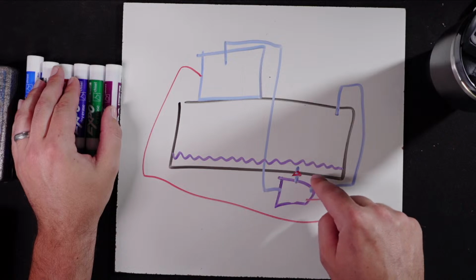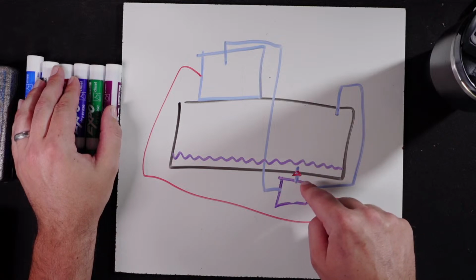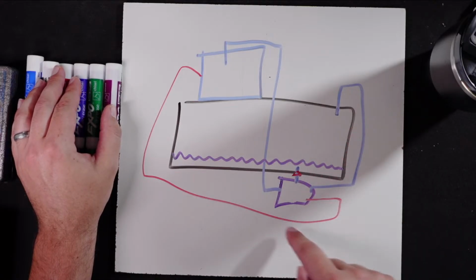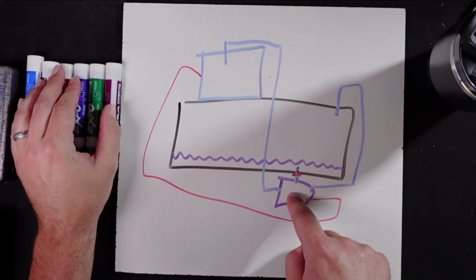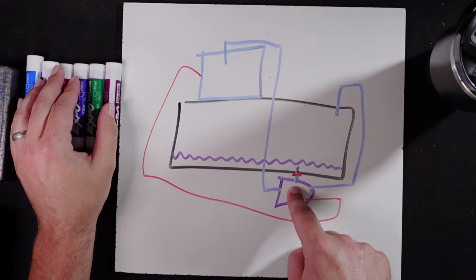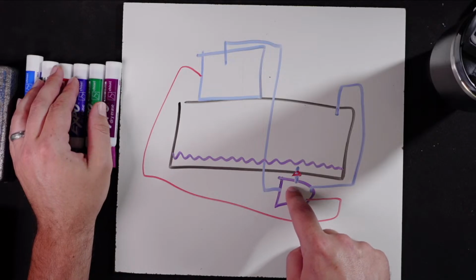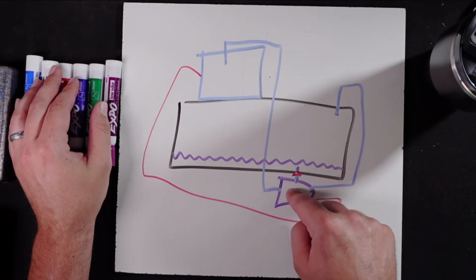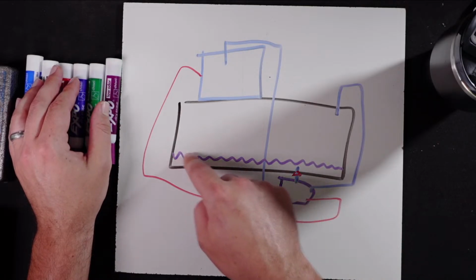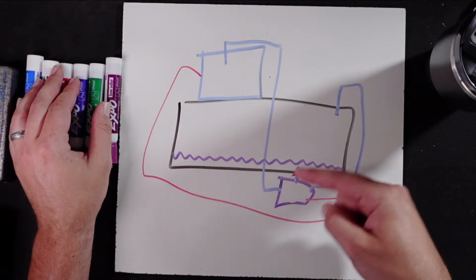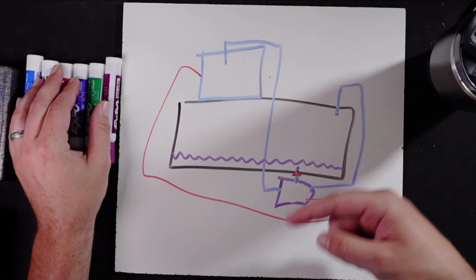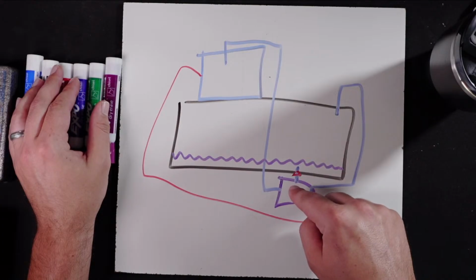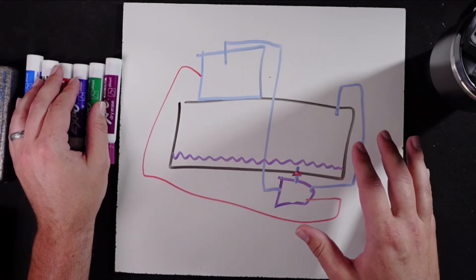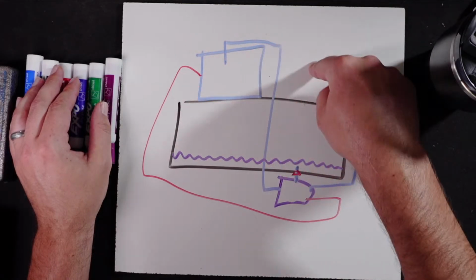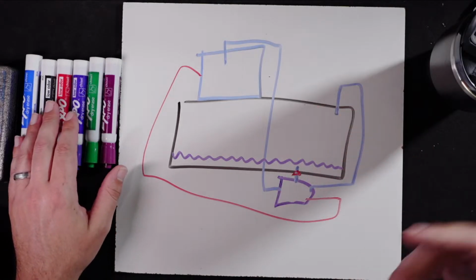And if this can't happen fast enough, or it's not going to happen that fast, is what I'm trying to say. Because we've got to fill this chamber, and this is on a time cycle, and I'd have to look at the books, but it's several minutes per cycle. Minutes per cycle. That is just one. And you got to think, a small volume of oil is actually getting captured into this chamber compared to what is stacking in the evaporator. And we need to get several cycles through, like a lot of cycles have to process through this pump in order to get the oil charge that's going to stack in here, even just from the startup process, back up to the compressor to return back into the oil separators to recycle back into the oil circuit.